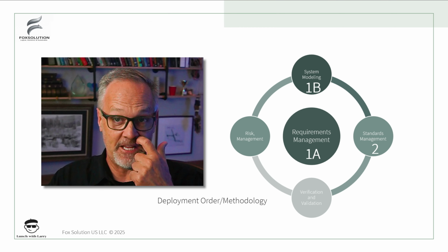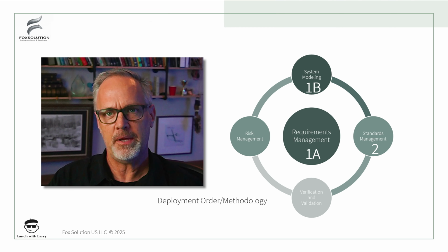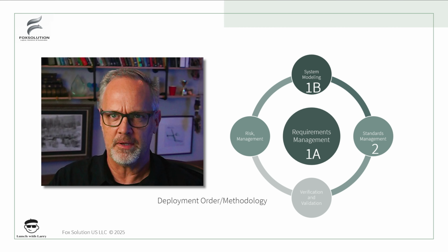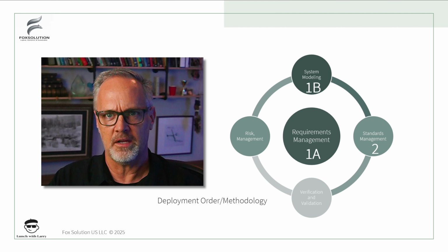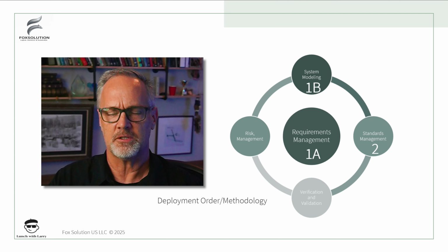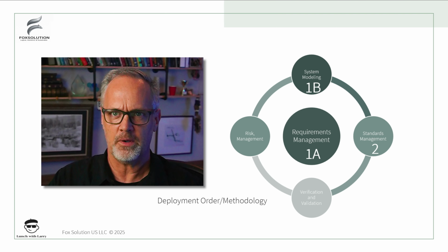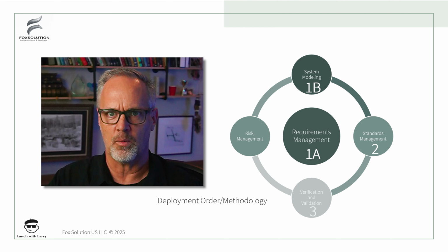Next thing is really standards management. How do we map in external standards to our requirements? And when I say external standards, I mean things like ISO 60601, electrical medical devices, ASTM standards, IEC standards, that kind of thing. So what is our industry view of the requirements? What would industry see as the right way to deploy any particular aspect of the design? We want to have that understanding built into the requirements as well.